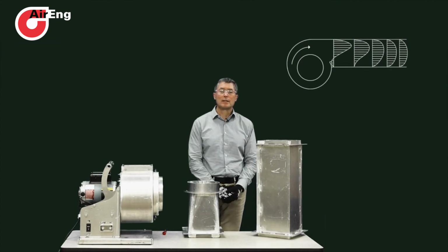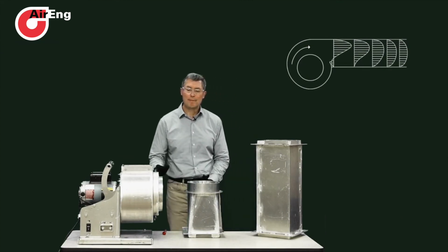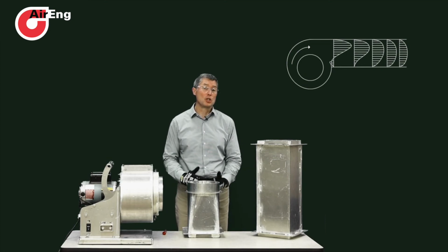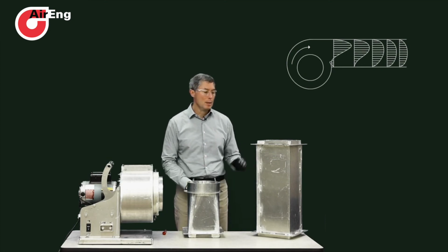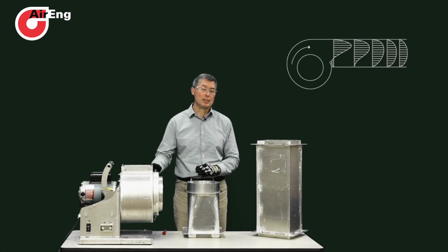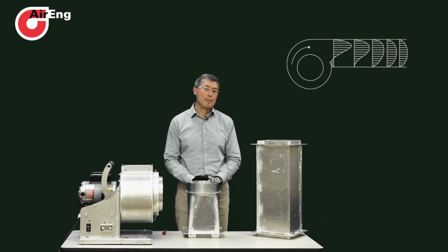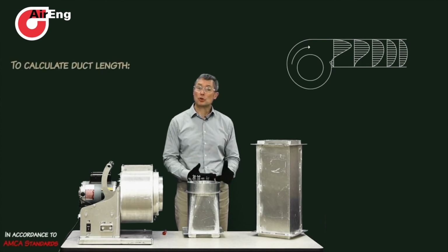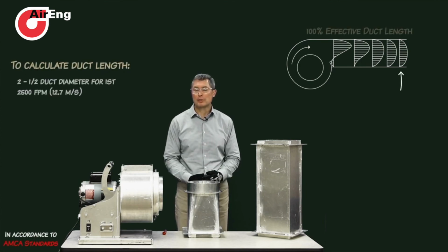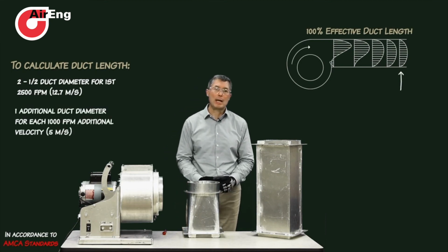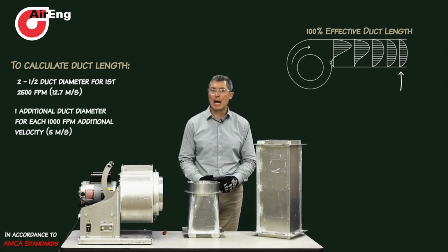Ductwork on the fan outlet has a pretty big effect on how the fan performs, just like ductwork on the fan inlet. You need to have an effective duct length in order for that velocity profile as it discharges from the fan to even out and get static pressure regain. AMCA Standard 201 tells us that we need to have 2.5 duct diameters for the first 2,500 feet per minute of velocity, and an additional duct diameter for each 1,000 feet per minute of velocity on top of it.